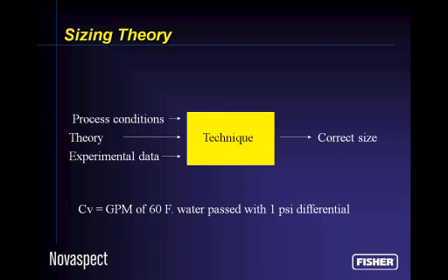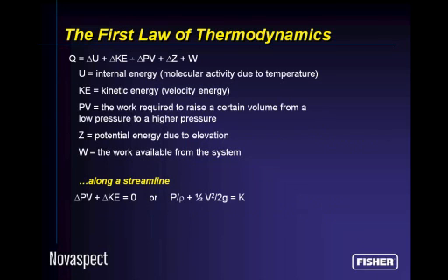By definition, 1 CV is equal to 1 gallon per minute of 60-degree water passing through the valve, which has a 1 psi difference in pressure from the inlet side to the outlet side. And I'm sorry to do this to you, but we couldn't possibly get into a discussion of flashing and cavitation unless we review a basic law that applies to these processes.